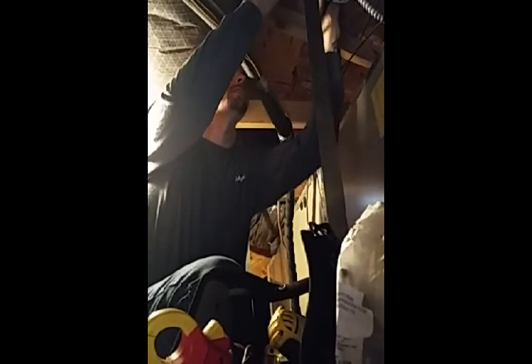So now what we'll do is take out this 60 amp. Well, it's not really considered a 60 amp, but it is rated for 60 amp, and it is a non-fused disconnect. The same disconnect as out at the condenser. And we will make sure all electrical connections inside are tight. Okay, after ensuring that all connections are tight, we'll go ahead and put the disconnect back together. And take off the panel.